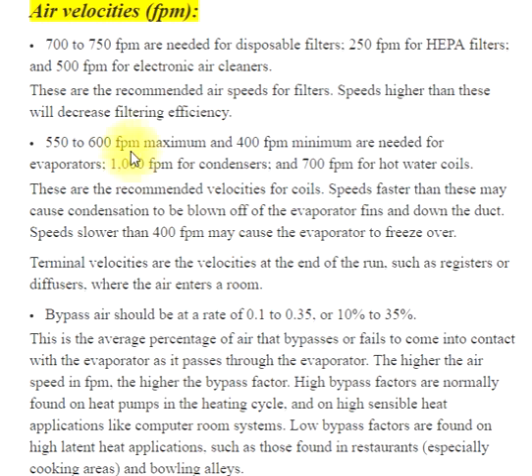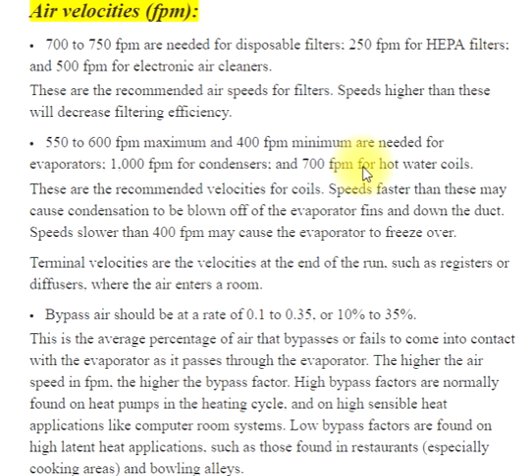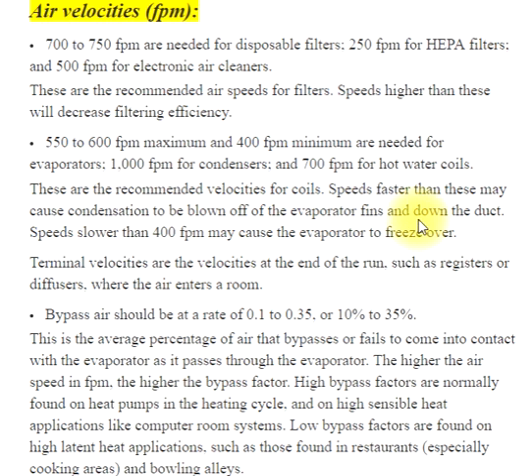550 to 600 FPM maximum and 400 FPM minimum are needed for evaporators, 1,000 FPM for condensers, and 700 FPM for hot water coils. These are the recommended velocities for coils. Speeds faster than these may cause condensation to be blown off of the evaporator fins and down the duct. Speeds slower than 400 FPM may cause the evaporator to freeze over.